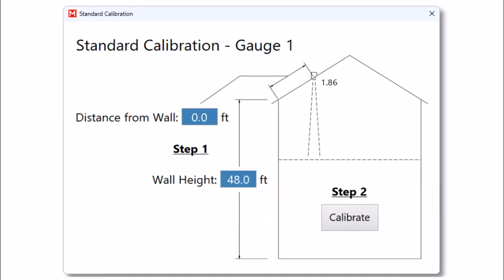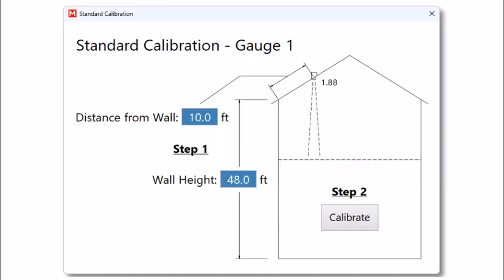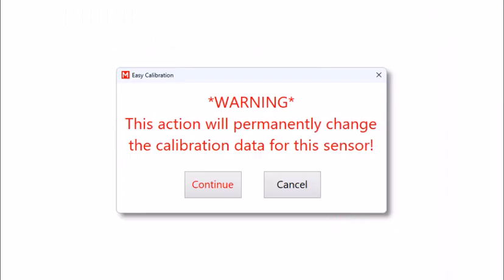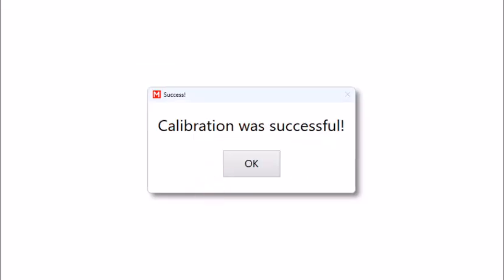then hit OK. For a standard calibration, you must also input the distance between the sensor and the edge of the bin. Do so by clicking on the top blue rectangle labeled Distance from Wall, entering the distance, then hitting OK. Now press Calibrate. Acknowledge the pop-up warning, and the sensor has now been calibrated using the standard calibration method.